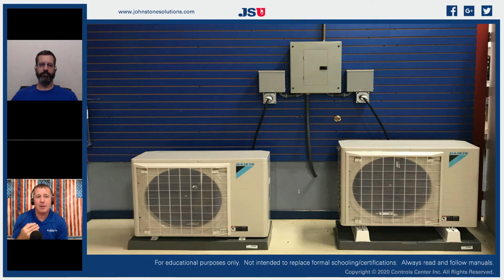So this gives me the opportunity to condition that voltage and bring that voltage down, because a lot of our inverter equipment actually has voltage ranges. And those voltage ranges are not as wide as you would think they were. A lot of them will be from like 208 to 250. And above that, they will actually start shutting themselves down. So I've seen inverter outdoor units that will shut themselves off on internal protection once they hit that 250, 253 volts. So having a conditioning unit on those inverters will get us out of those situations.